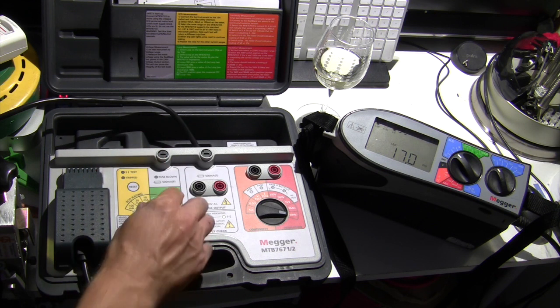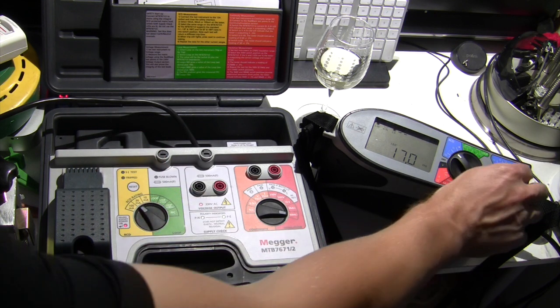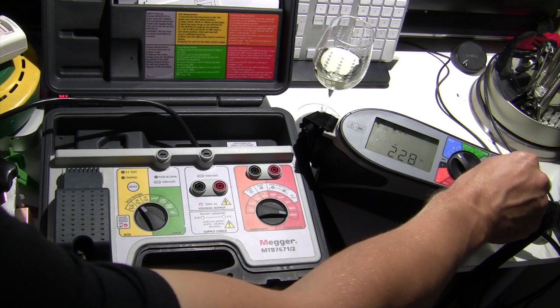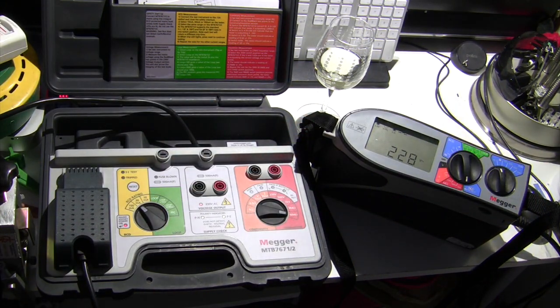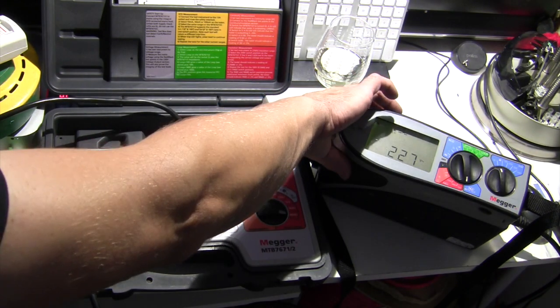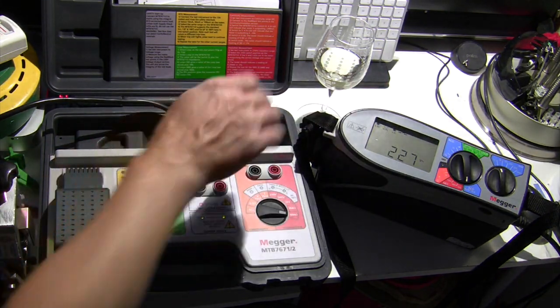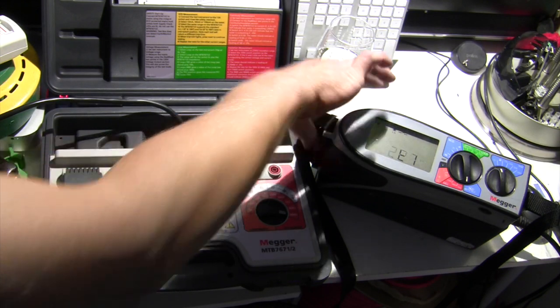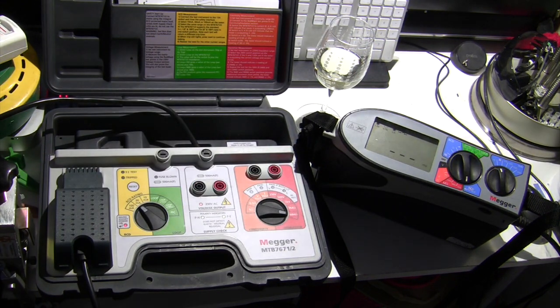Now I'm going to do all this again, but this time at 30 milliamps, and this time on the auto RCD setting, just because it's a hell of a lot quicker and saves me having to push a load of buttons. Obviously every time it clicks off I've still got to reset it, but if we kick it off it's going to do its half times test. So it's going to send 15 milliamps down there, and it shouldn't trip within 2 seconds from what this tester records, and there we go, it's passed that.